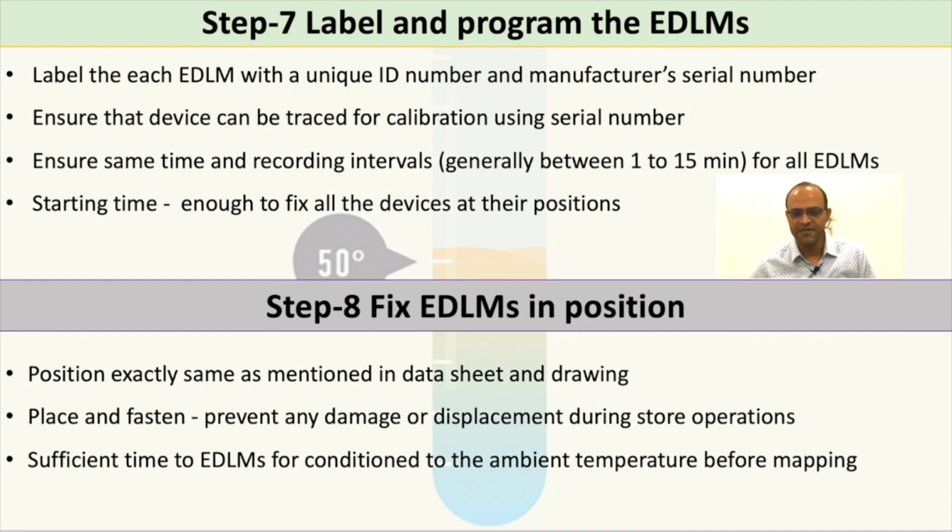Step 8. Fix the EDLMs in position. Position them exactly as mentioned in the data sheets and drawing. Place and fasten them. Prevent any damage or displacement during the storage operation. Allow sufficient time for the EDLMs to condition to the ambient before mapping.